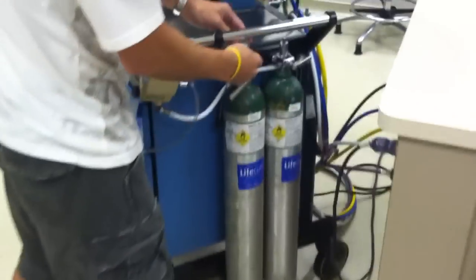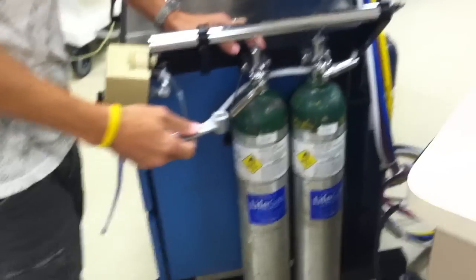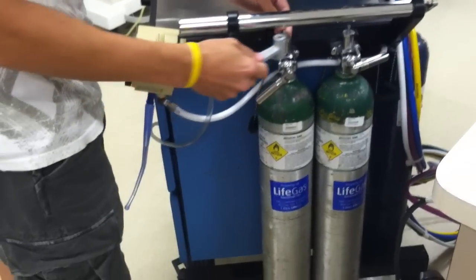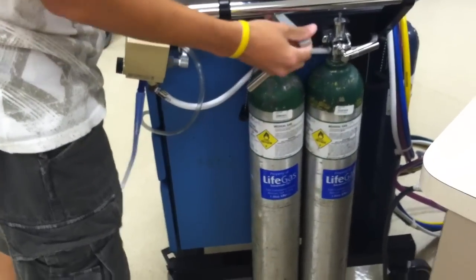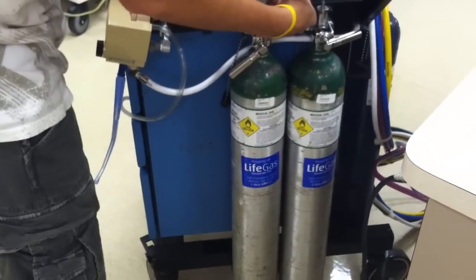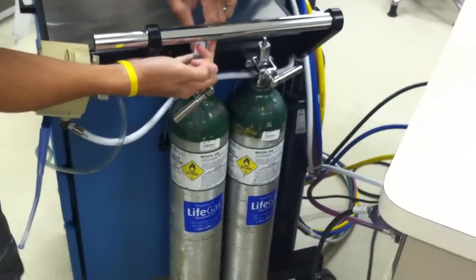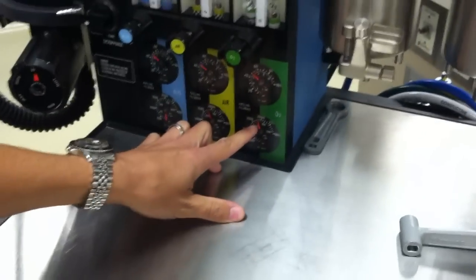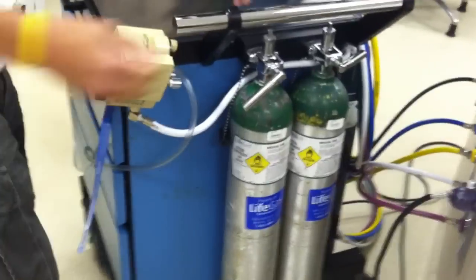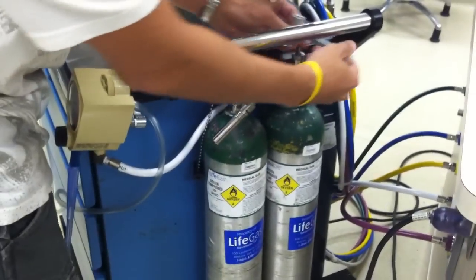We have a special note here for oxygen. This machine has 2 E-cylinders for oxygen. This can be on any machine, new or old. What you want to do is you open up the first one, close it, and check the pressure. So this one is a little under 2,000 psi. Now if I open up the next one, I'm not going to know what my pressure is, and I'm going to explain that real quick to you.